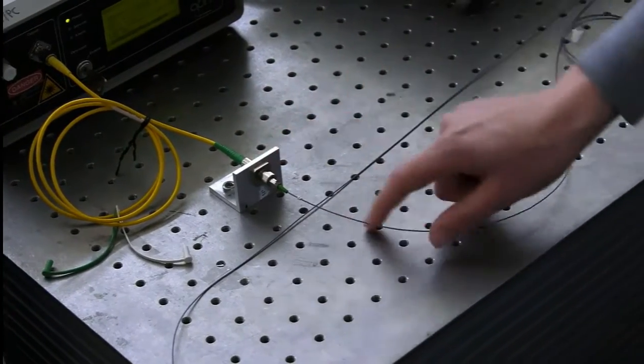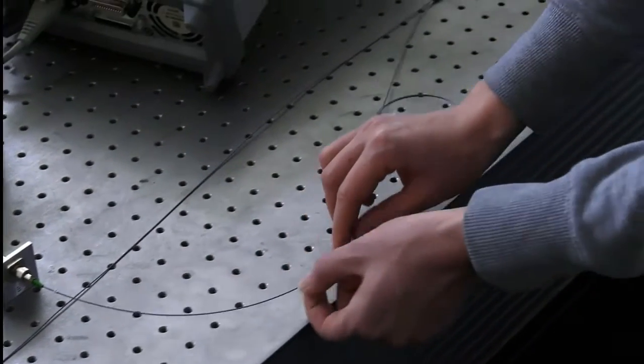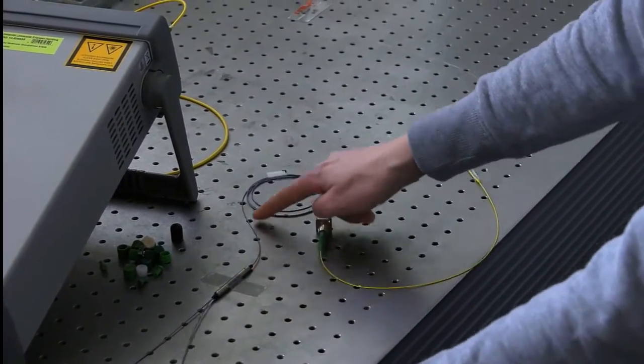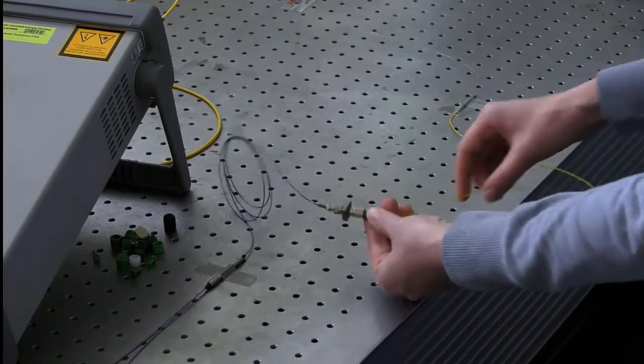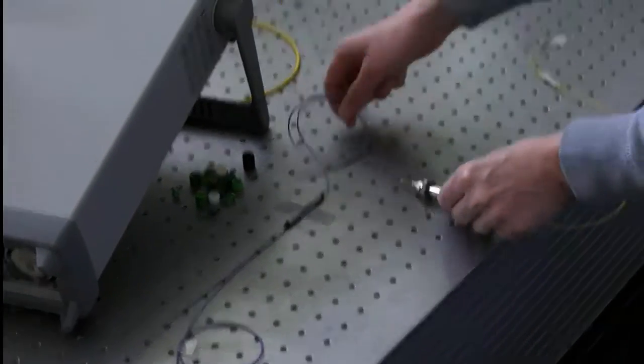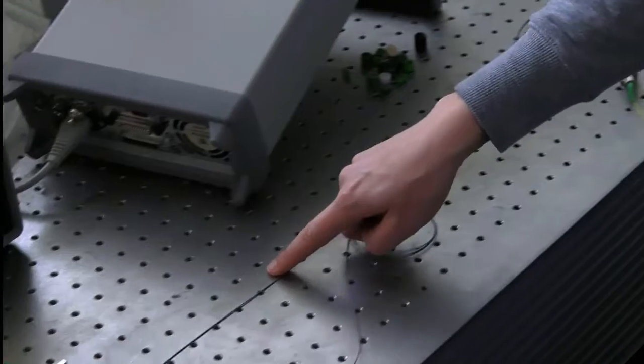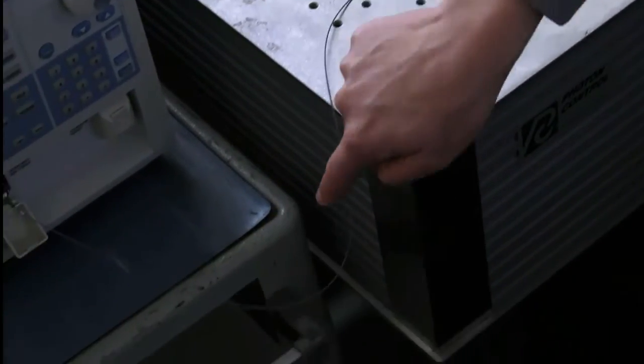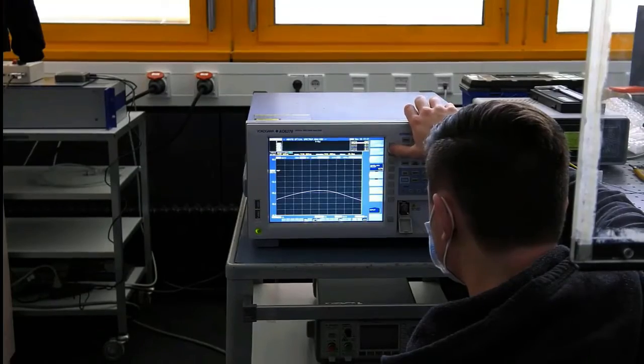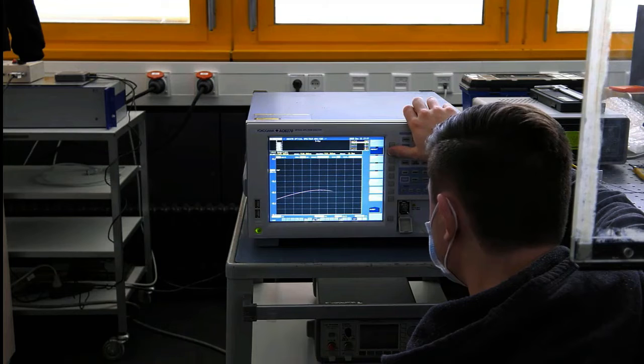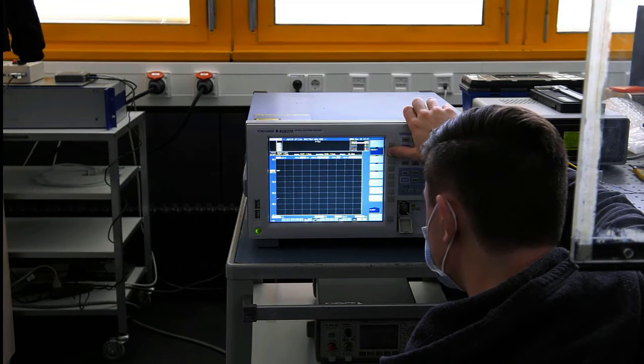To determine the reflectivity of the FBG and monitor the inscription process, we use a setup consisting of an Erbium-doped fiber amplifier as a broadband light source connected to a fiber-coupled circulator that guides the light to the photosensitive fiber. The back-reflected light from the FBG passes the circulator again and is detected by an optical spectrum analyzer, OSA for short. If no grating is inscribed, we will only get a back reflection of the characteristic light source spectrum from the perpendicular fiber end face.